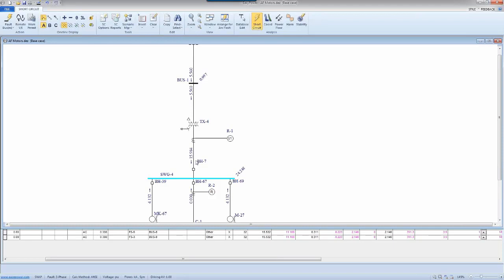But regardless of the details, regardless of what type of relay it is, going through the steps: number one, you need the bolted fault current on the bus. Number two, you would need the trip time. One little thing that I left out here is the bus. The total fault current on the bus is not necessarily equal to the fault current coming from this branch. It might be different, as you can see here, because you have more than one branch contributing to that specific bus.